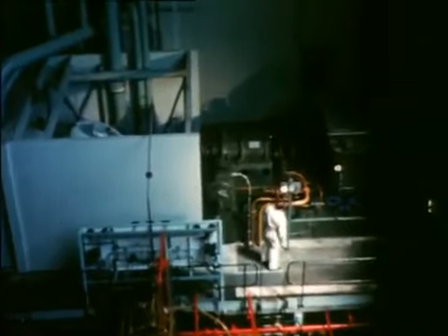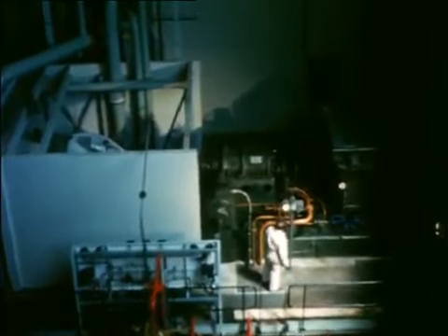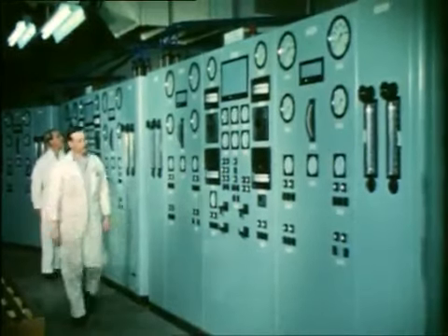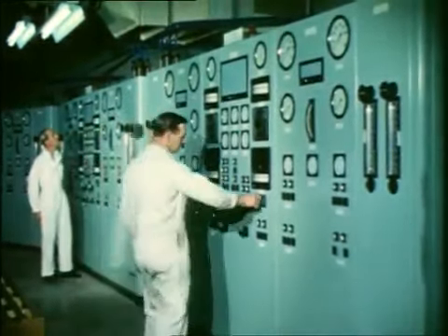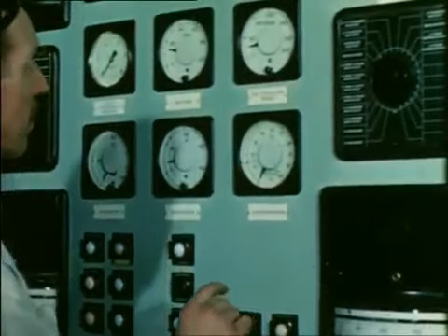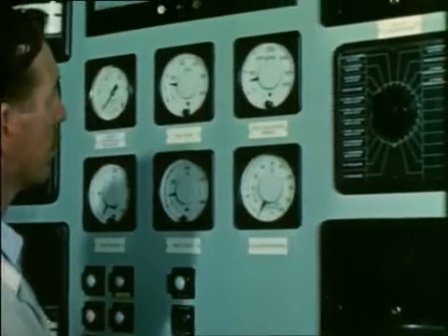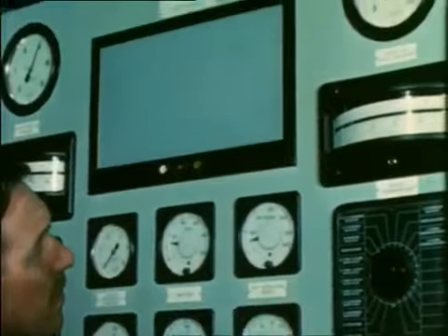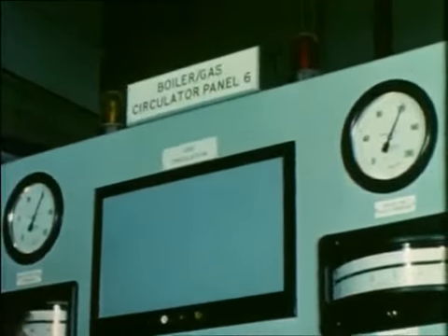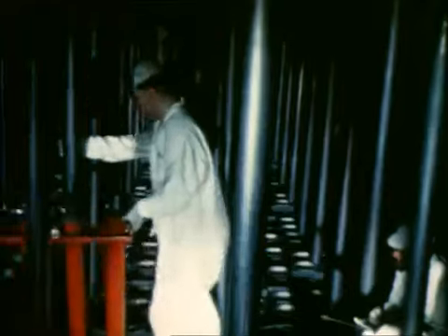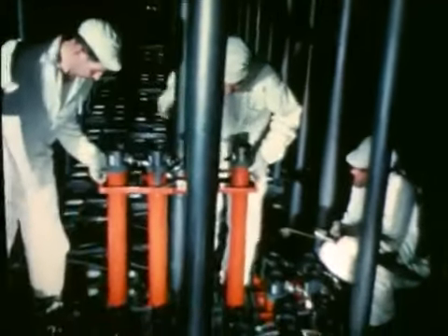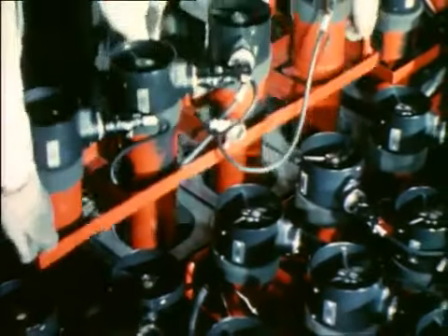First, the 8 blowers were started up and run at full speed. Pressure tests were then made on the gas circuits and pressure vessel. To check and confirm the volume of gas passing through each fuel channel, air was blown through the gas circuits by the blowers and the flow measured by anemometers placed at the top of the fuel channels and recorded electronically.